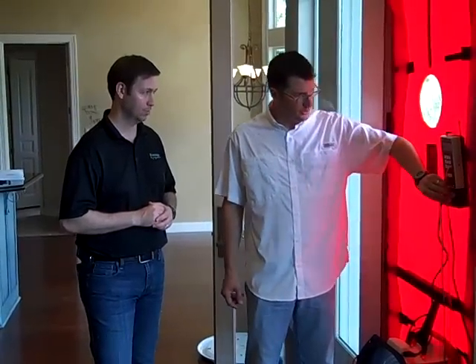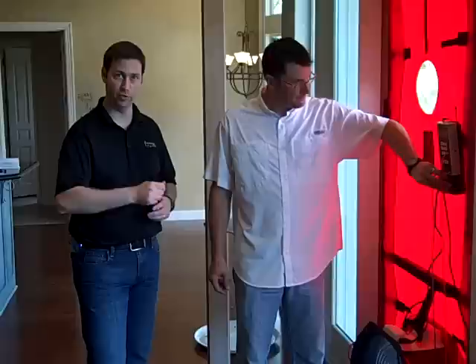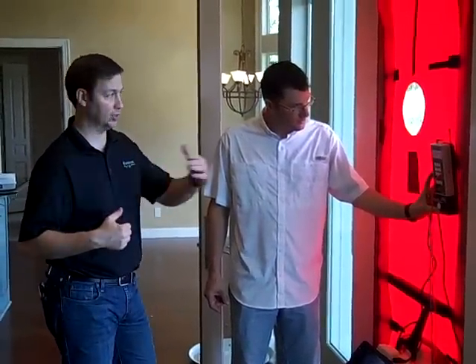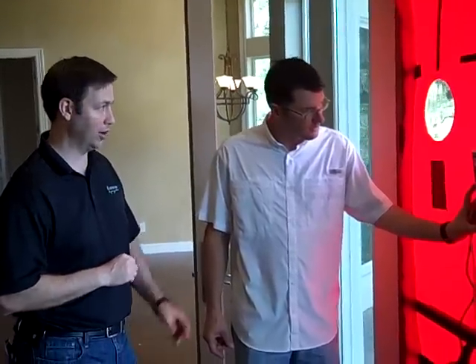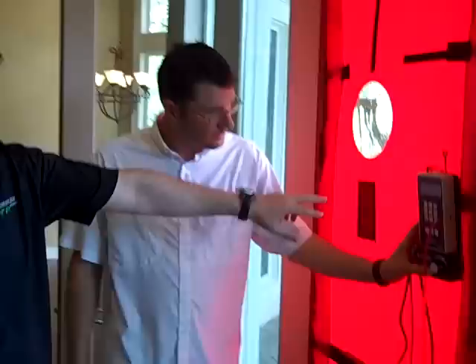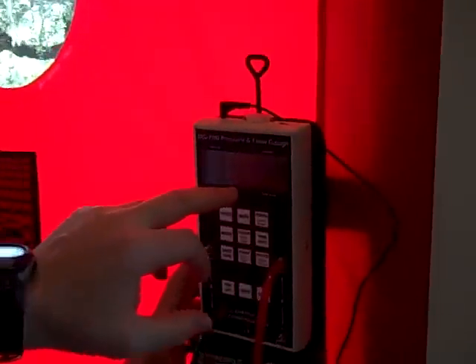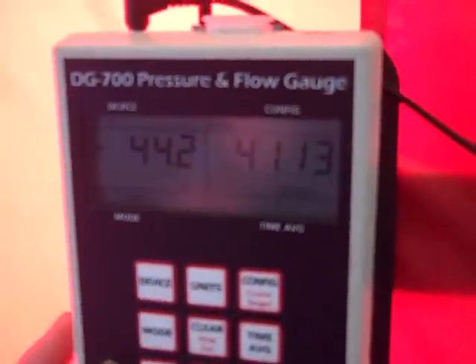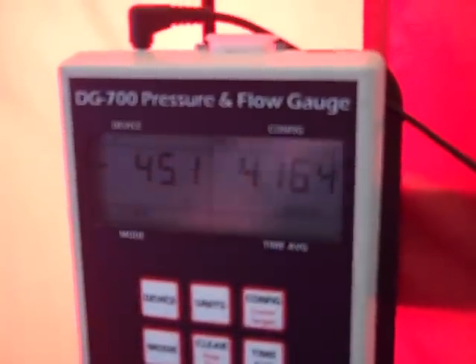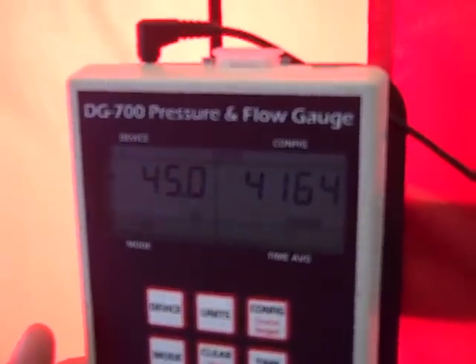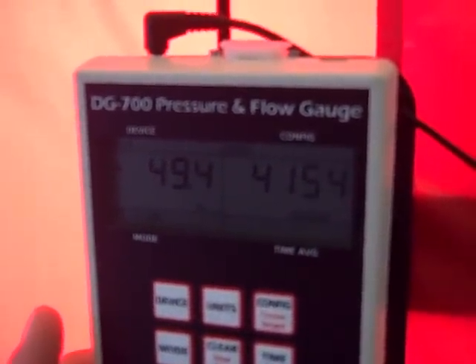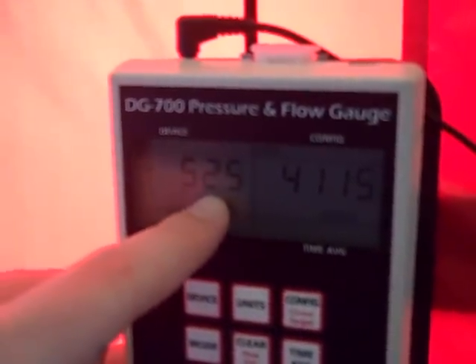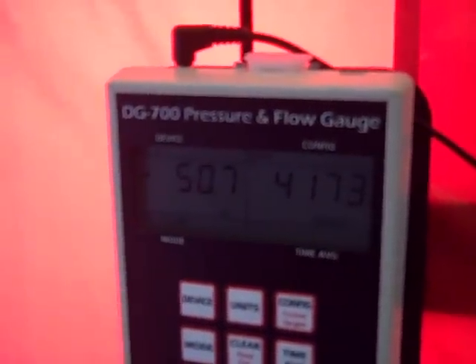So we'll take the house to negative 50 pascals — cranking up to 50 pascals of air pressure differential between the inside of the house and the outside. It's about to get loud. The pascal rating is on your left here, and the CFM 50 rating is on the right. This fan is moving about 4,000 CFMs right now at 50 pascals of pressure — we're actually at 53, 52 pascals — he's bringing it down just slightly.